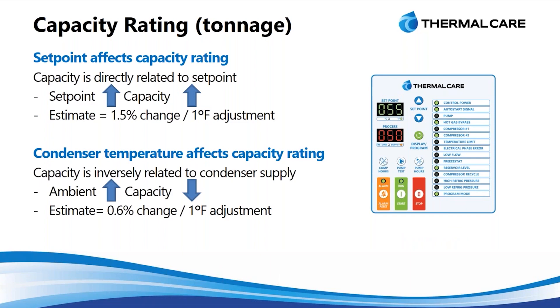The other aspect of a nominal rating is the ambient temperature or the cooling tower and cooling water condenser, and those are actually inversely related. As that ambient temperature goes up — as it gets hotter in the air surrounding the chiller — it's more difficult for the chiller to reject energy out, so it has to work harder and the capacity goes down. Both the water and the air, as they go up or down, affect that capacity. When you really think about this, it's about the location of where you're going to put the chiller.